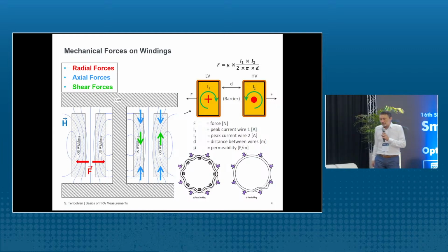So first of all, you have mechanical forces on the winding. If you have a conductor and a current is flowing through the conductor and it's within a magnetic field, you have forces on the conductor. That's the principle of an electrical motor. And of course you have in a transformer a magnetic field, and you have also conductors where current is flowing. And in case you have, for example, a short circuit, the current is very high. And then also quite strong forces appear on the windings.